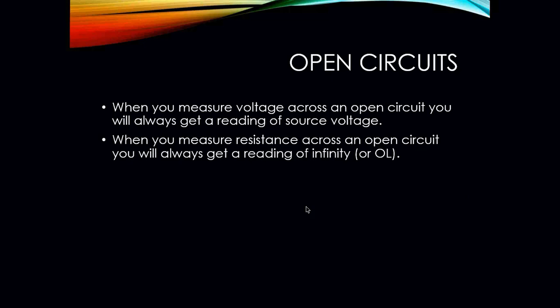When you measure voltage across an open circuit, you will always get a reading of source voltage. Whatever that voltage reading is, if that switch is open, you are going to read source voltage. That source voltage is power that is coming into the circuit. So for example, 24 volts. If my circuit is operating off of 24 volts and that switch is open, I would read 24 volts across that switch. When I measure resistance across an open switch, I'm always going to read OL, or open load. That's telling me that the switch is open. I cannot continue on with my path.